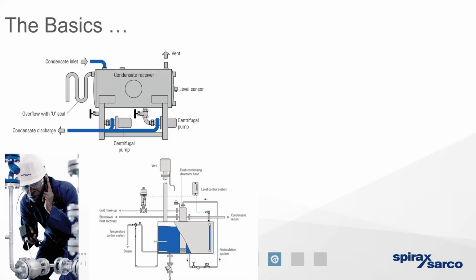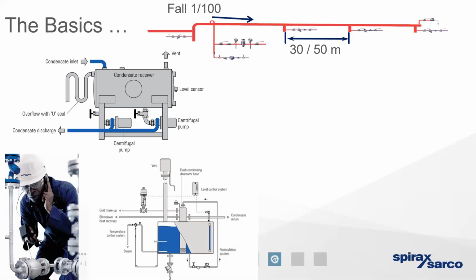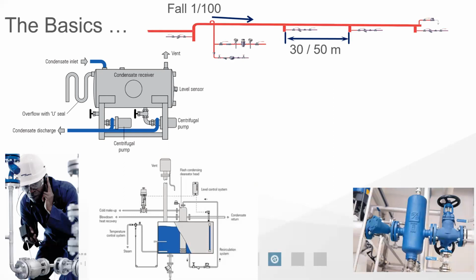We also want to ensure that we're observing good working practice to recover as much of the condensate as we possibly can, to ensure that we don't have the pumps in the cavitated or failed position, and to ensure that we don't have significant amounts of condensate being lost through the vent wherever there's that pressure drop in the condensate. Good working practice also means keeping the steam as dry as possible, ensuring that it can drain out of the distribution network to the steam traps quickly, and ensuring that we're fitting separators at the appropriate key points to dry the steam. Those key points are immediately behind the steam boiler, where we get a fluctuation in pressure and temperature and we get wet steam being produced, immediately ahead of the process, and also ahead of any capital equipment to protect it. The drier the steam, the more energy there is present in it.